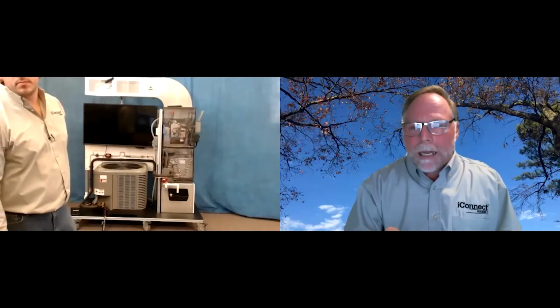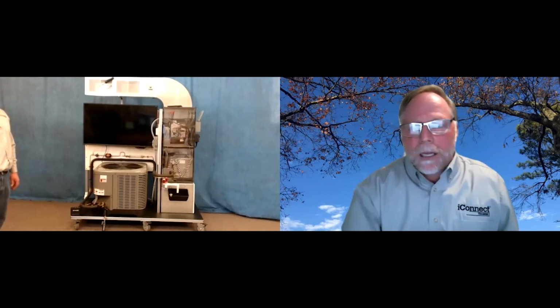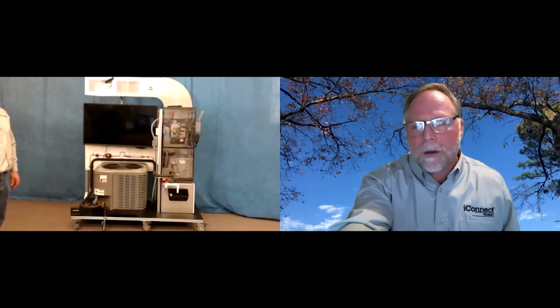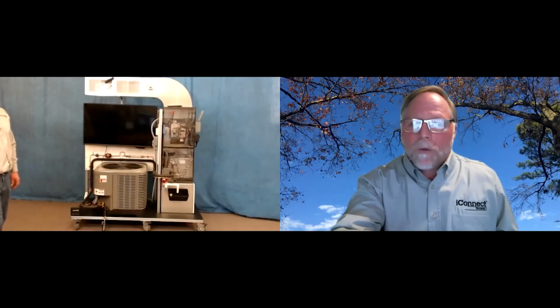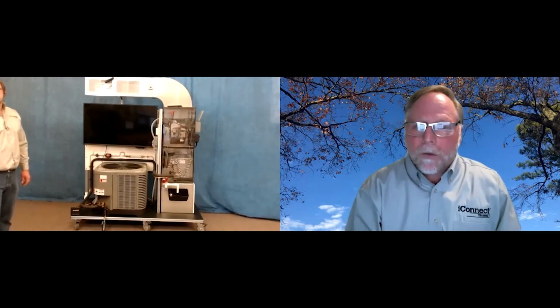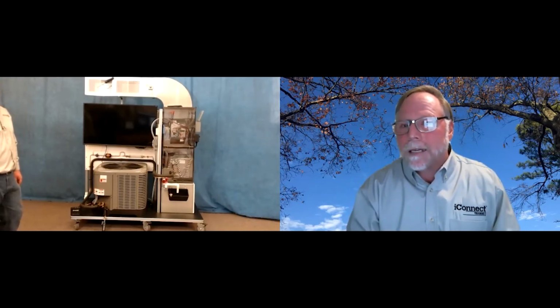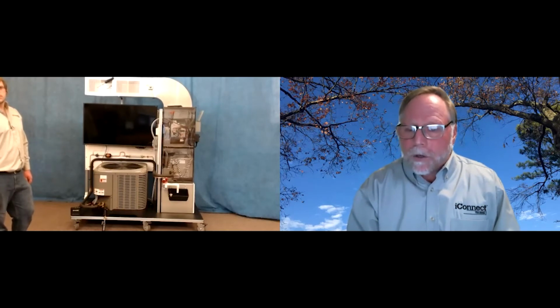So Nick, I want to talk about the data that you have right there at your fingertips for this unit on the app. On the left side, you've got your suction pressure. You've even got a visual indicator of where it is on a gauge on the outside edges. Also, you've got your saturation temperature right there with the pressure. And on the high side, we're running about 226 PSIG, and that is showing about a 77 to 78 saturation temperature. So immediately the students can see that as it's operating.